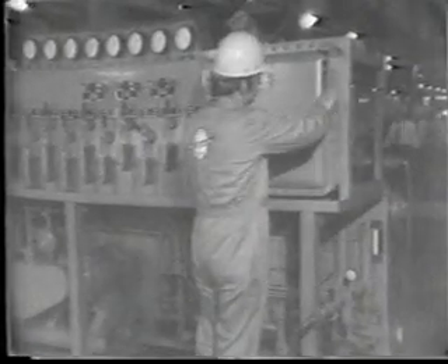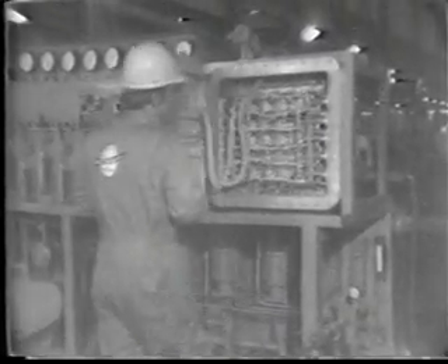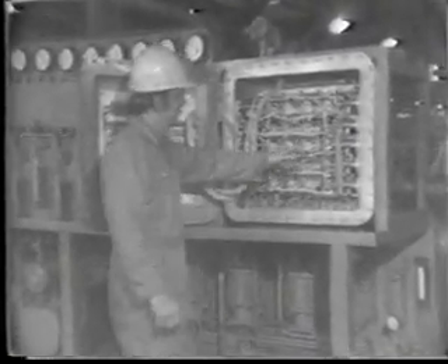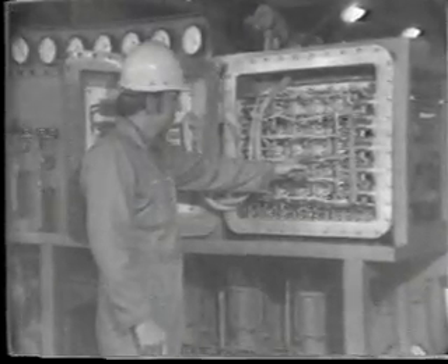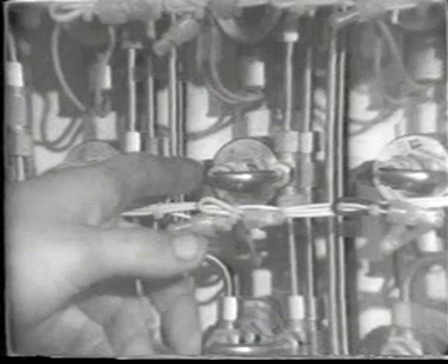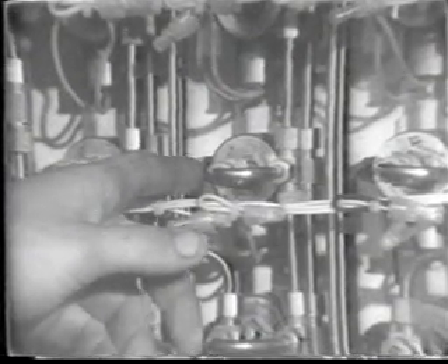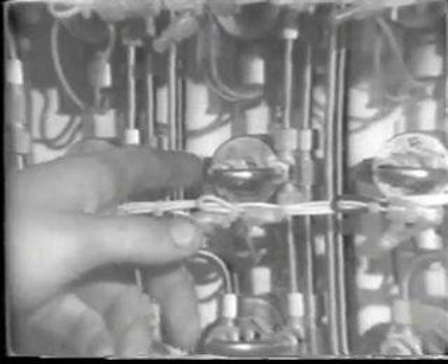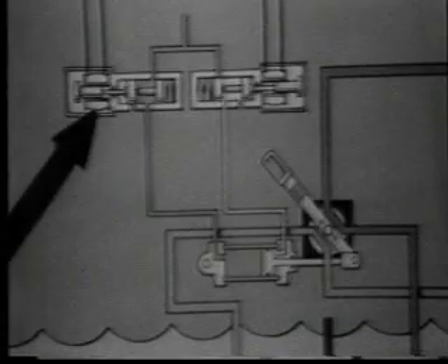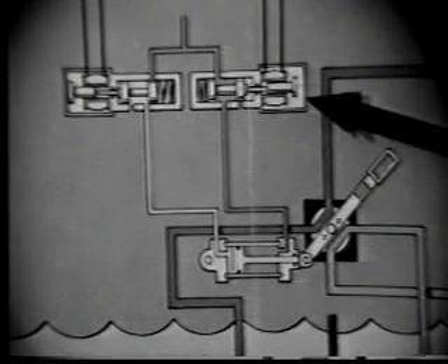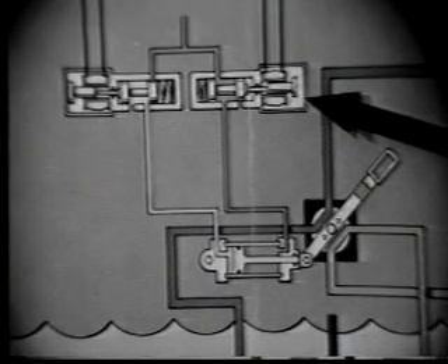With one exception, all of the system's solenoids are located in the right-hand explosion-proof box on the hydraulic control manifold. These solenoids are used to operate an air cylinder, which in turn operates a function. Each function on the front of the hydraulic control manifold has two solenoids, one to open the function and one to close it. These solenoids are energized by the corresponding push buttons on the remote panels.